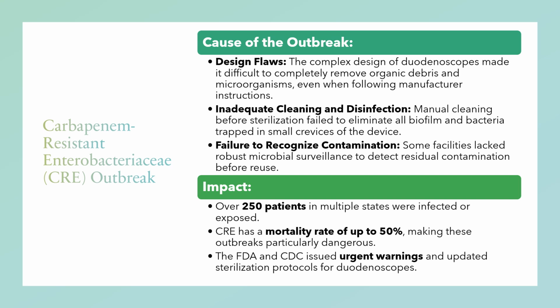Because you're not able to properly clean the instrument and get into all those crevices, bacteria and biofilm were trapped inside the small areas. This allowed over 250 patients to become infected or exposed to CRE. Now, CRE is especially dangerous because it has a mortality rate of up to 50%. So the FDA and CDC issued urgent warnings and updated the sterilization protocols for duodenoscopes.